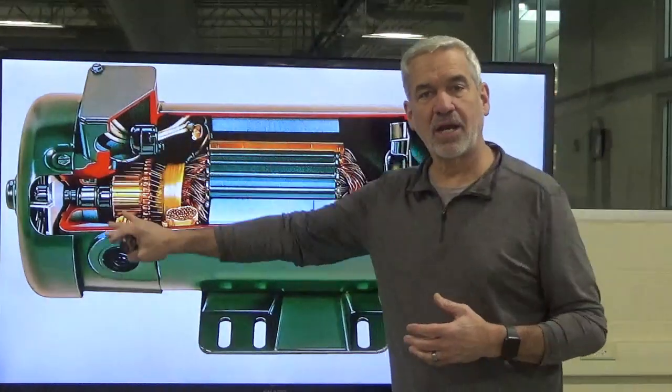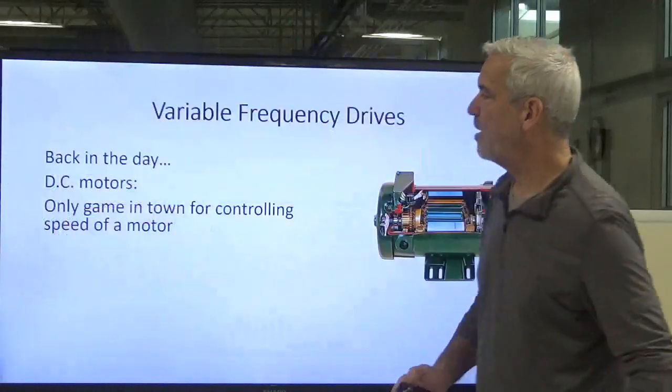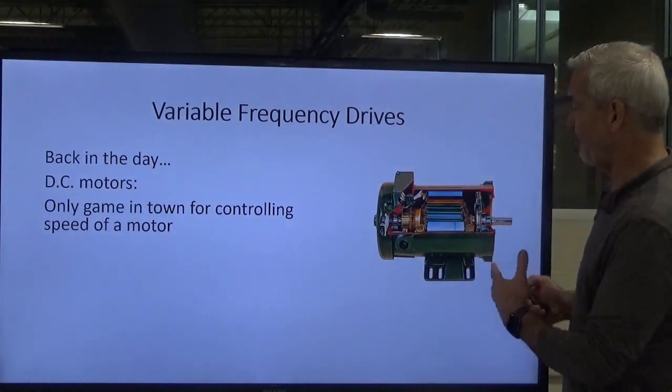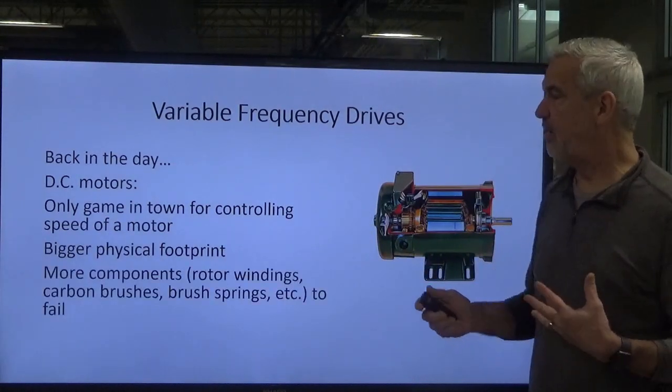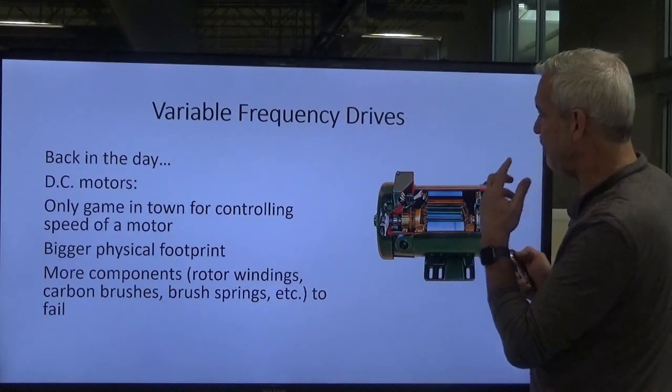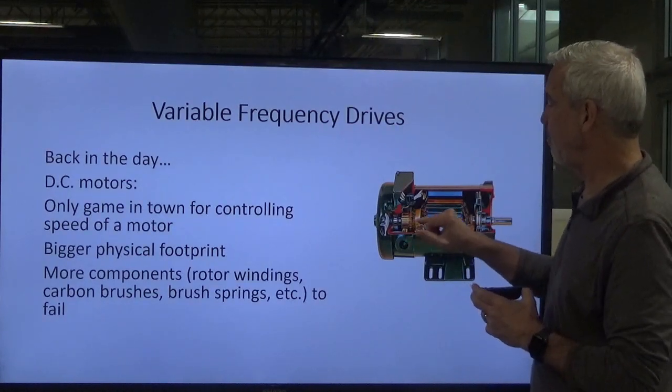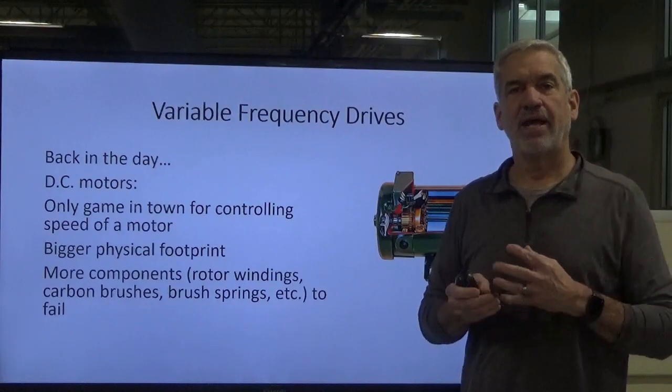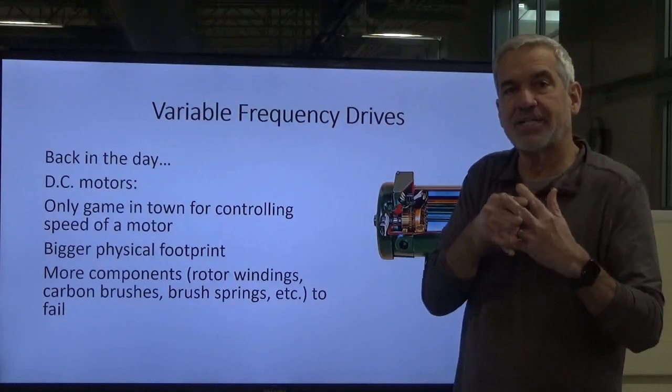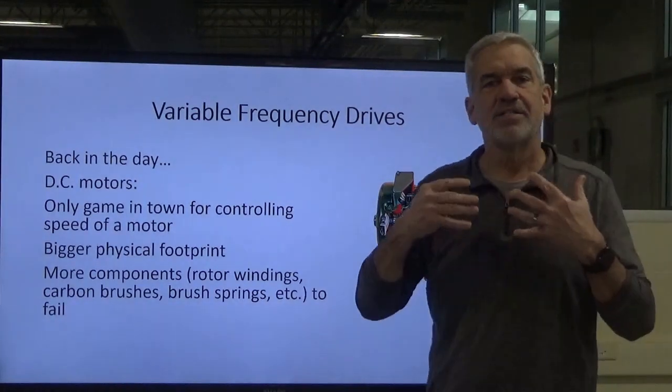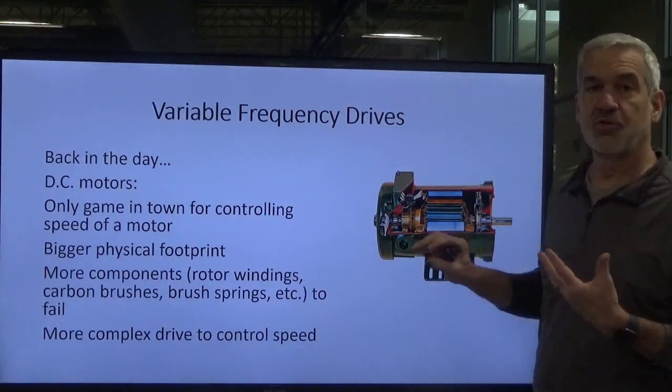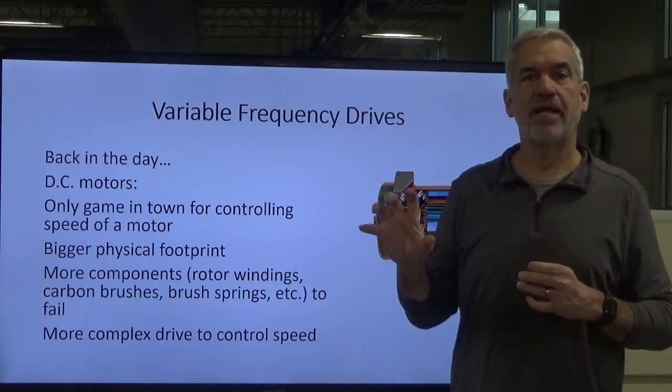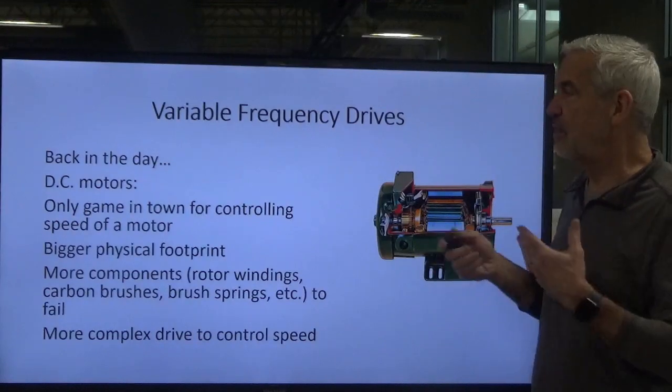This is a picture of a DC motor, a direct current motor. Very large and complex in its makeup. Back in the day, this was the only way you could control the speed of a motor. They were really large physically with a lot more components. This motor has carbon brushes that conduct electricity between the rotor and the stator windings. The carbon brushes would wear, and the commutator would glaze over and have to be resurfaced. There was a lot of arcing, a lot of maintenance involved. But at that time, it was the only way to control motor speed. AC motors were strictly one speed, full speed, and that was it.